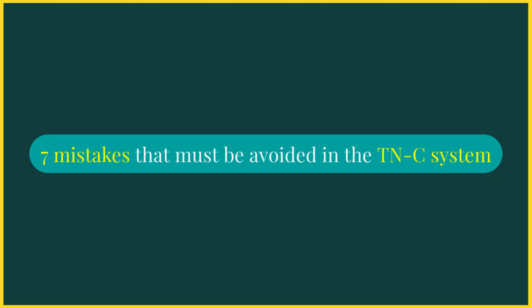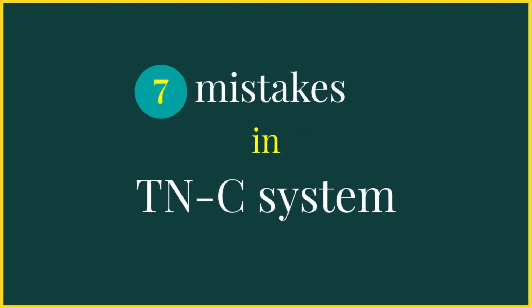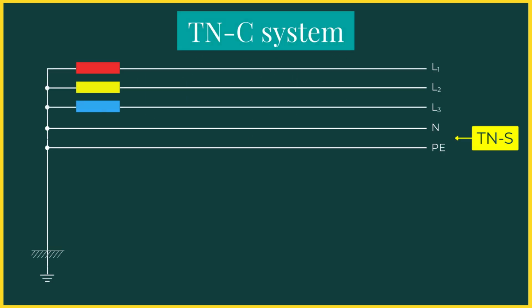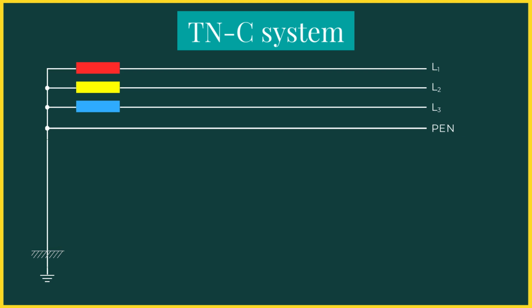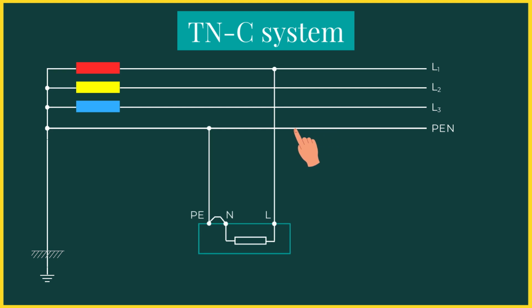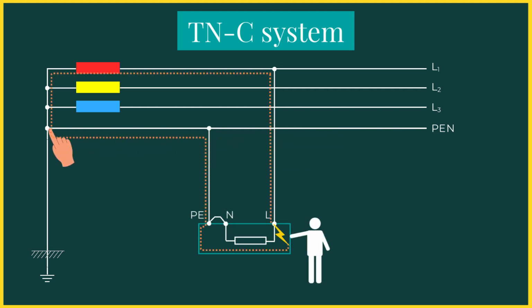In this video, we will examine 7 mistakes that must be avoided in the TNC system. To understand where these mistakes occur, and why they can be dangerous, we must first recall what fundamentally defines a TNC system. In a TNC system, the neutral conductor and the protective conductor are combined into a single conductor, known as the PEN conductor. In other words, the same conductor is used for both the neutral and the protective earth. It carries normal load current, and it also protects people from electric shock. This is why the TNC system has specific rules that must be followed.